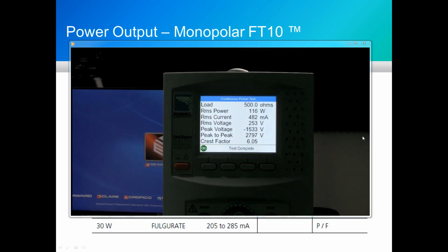Now, a quick comment on this. When we're doing a manual test, as we just did, that information will not be saved in memory. We have test sequences all set for a bunch of different generators, a lot of different manufacturers, models. And when you do one of those test sequences, the first thing the generator or the analyzer will ask you for is to enter the asset number. So all of that test data that you just saw is associated to a certain asset number. And there you then have your data traceability.